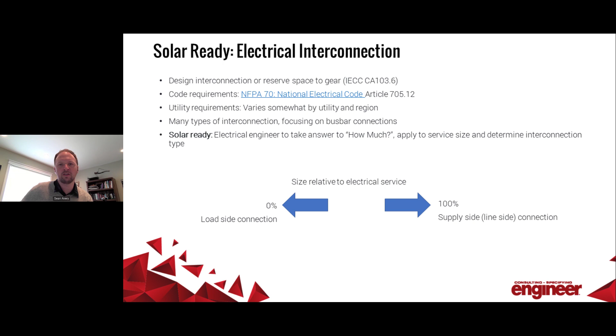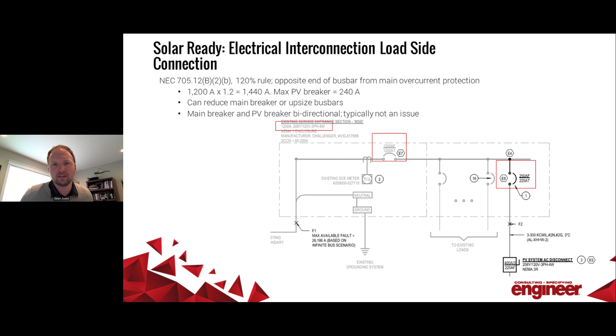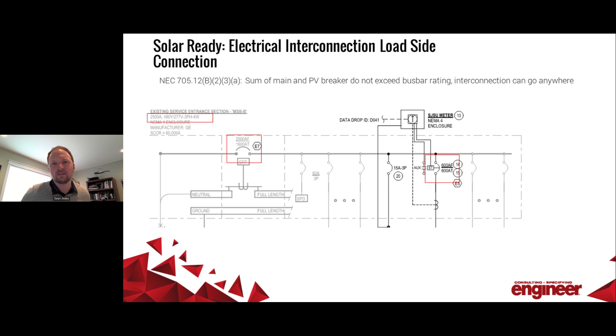For load side connections, the most commonly used one is the 120% rule, which means I can locate the PV point of interconnection at the opposite end of the bus bar from the main service disconnect. And if I sum those two up, they cannot exceed 120% of the rating of the bus. Another way around this is you could either upsize the bus compared to the main breaker or reduce the main breaker so that it's smaller than the bus. Then the sum of those together can be 100%, and you can put the solar anywhere on that bus that you like. These are the easiest ones in a retrofit, and if your system size is relatively small compared to the service, it's the easiest to implement.